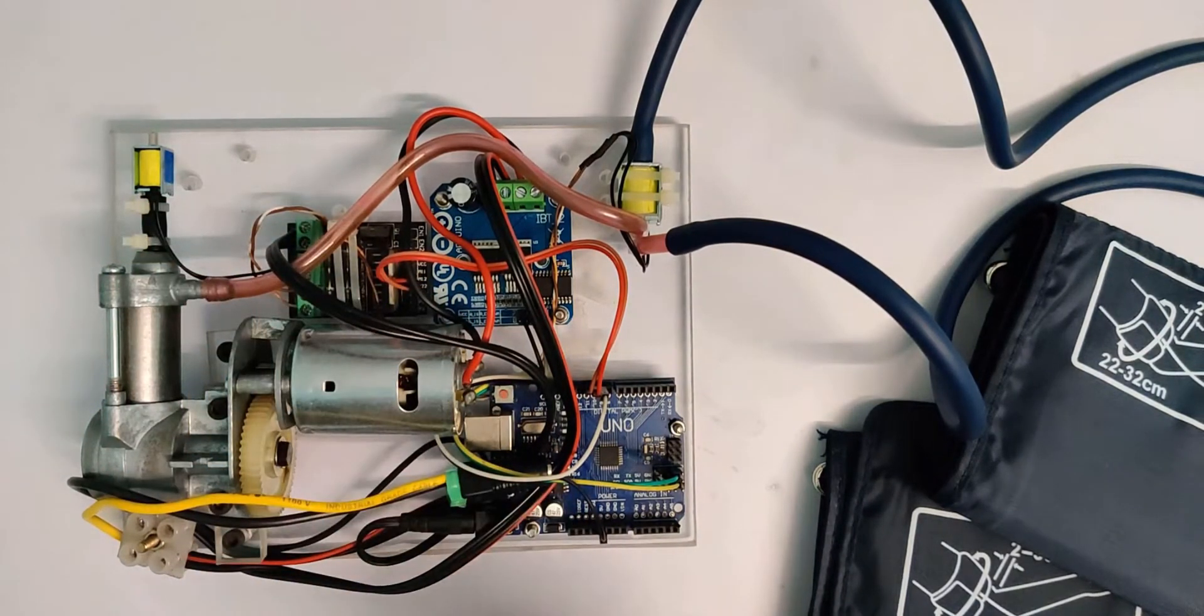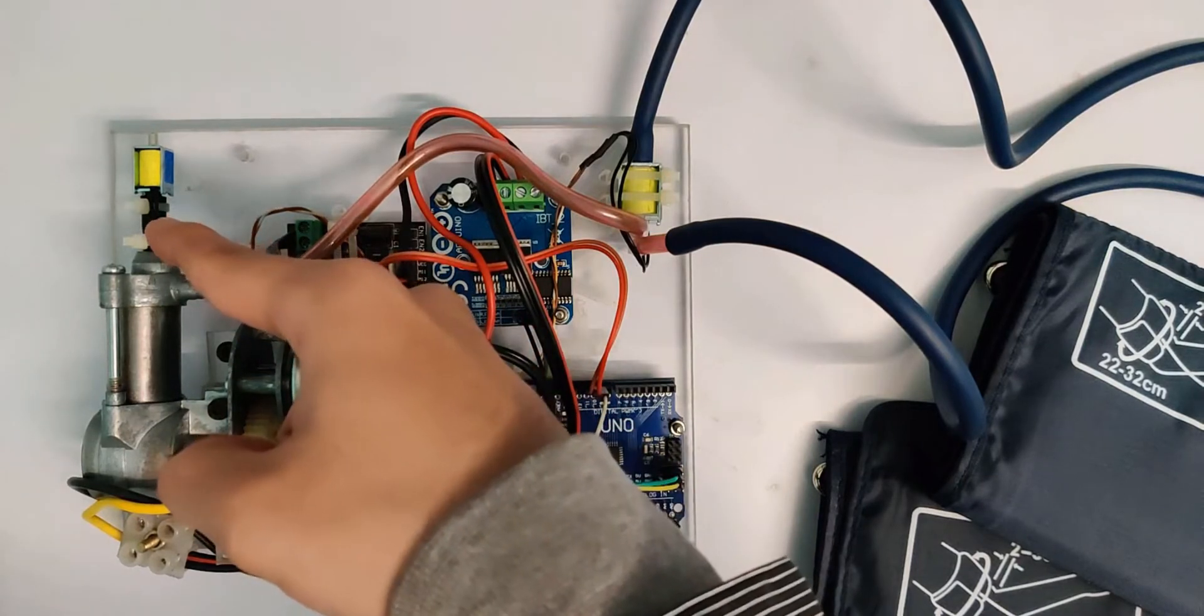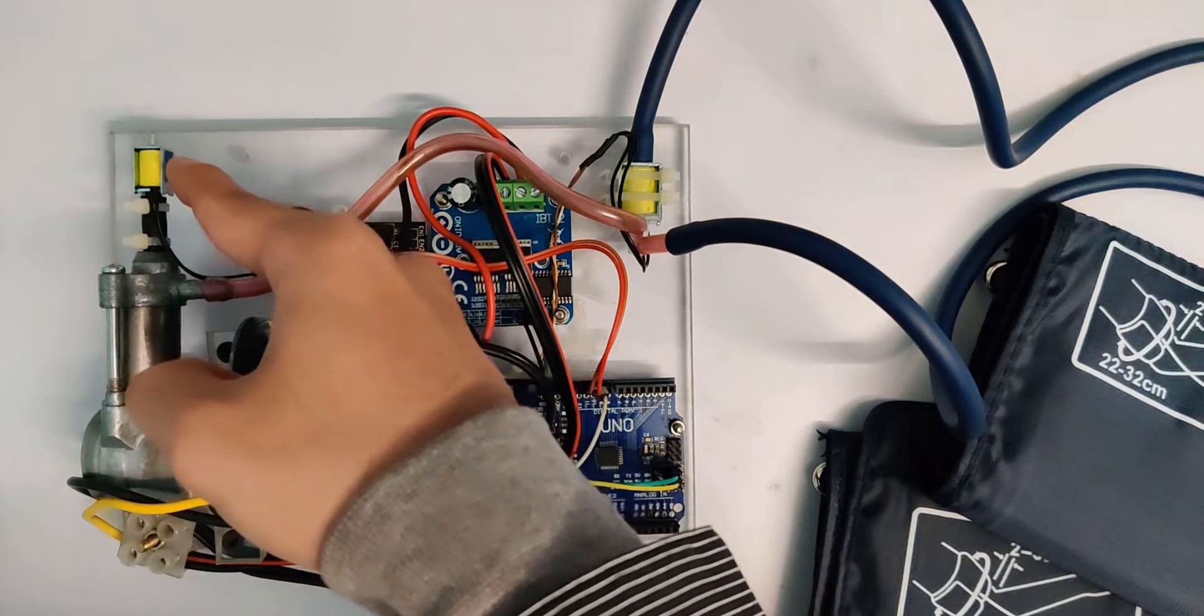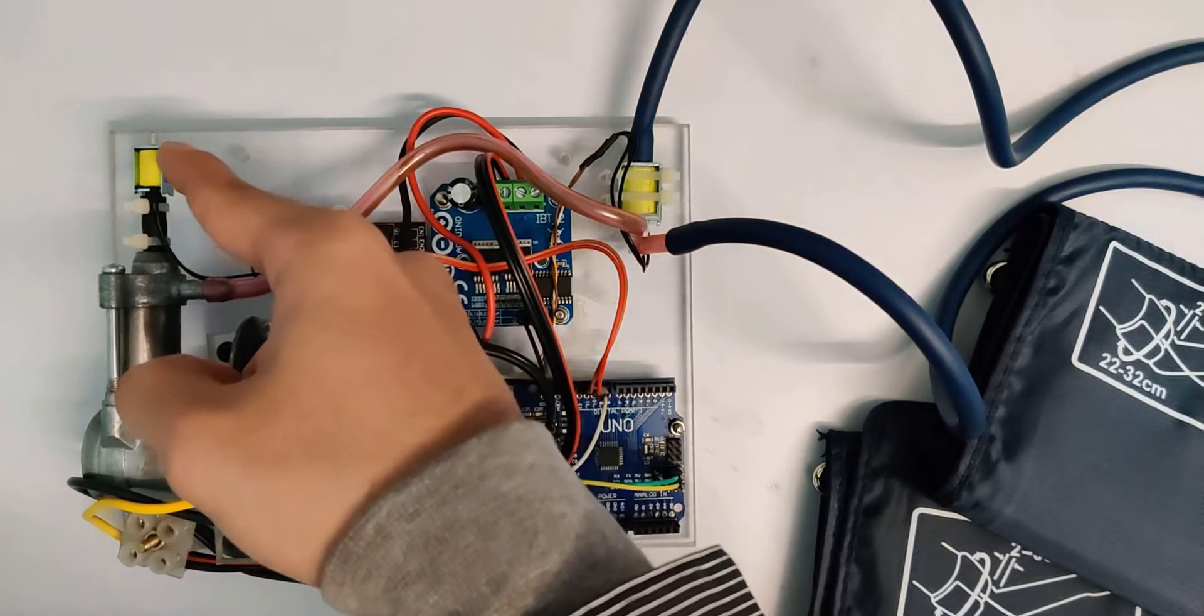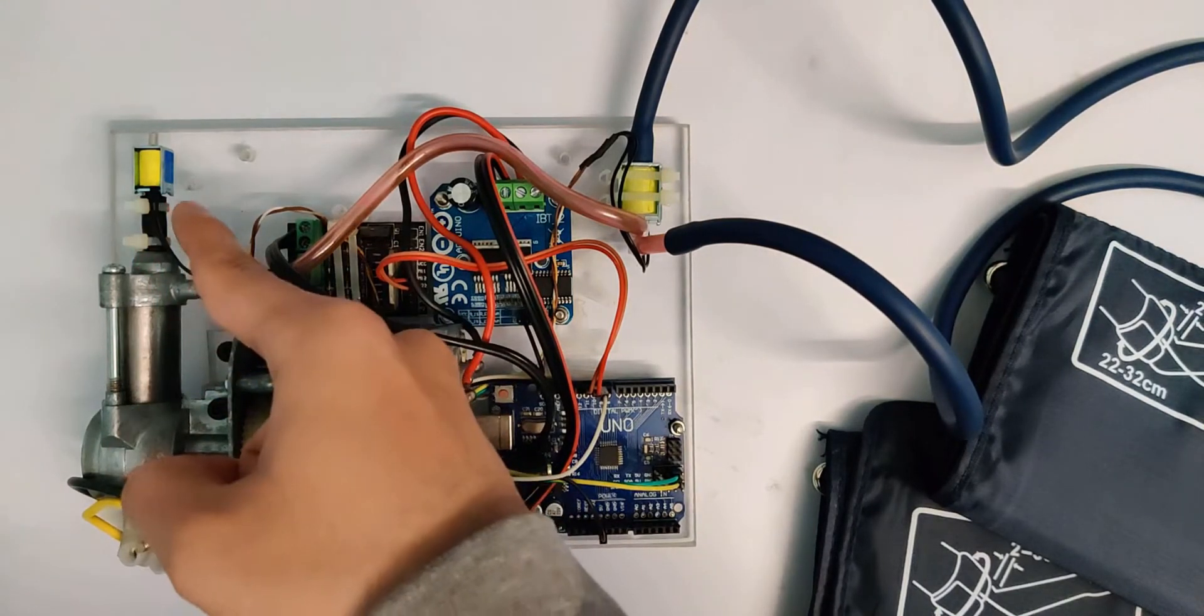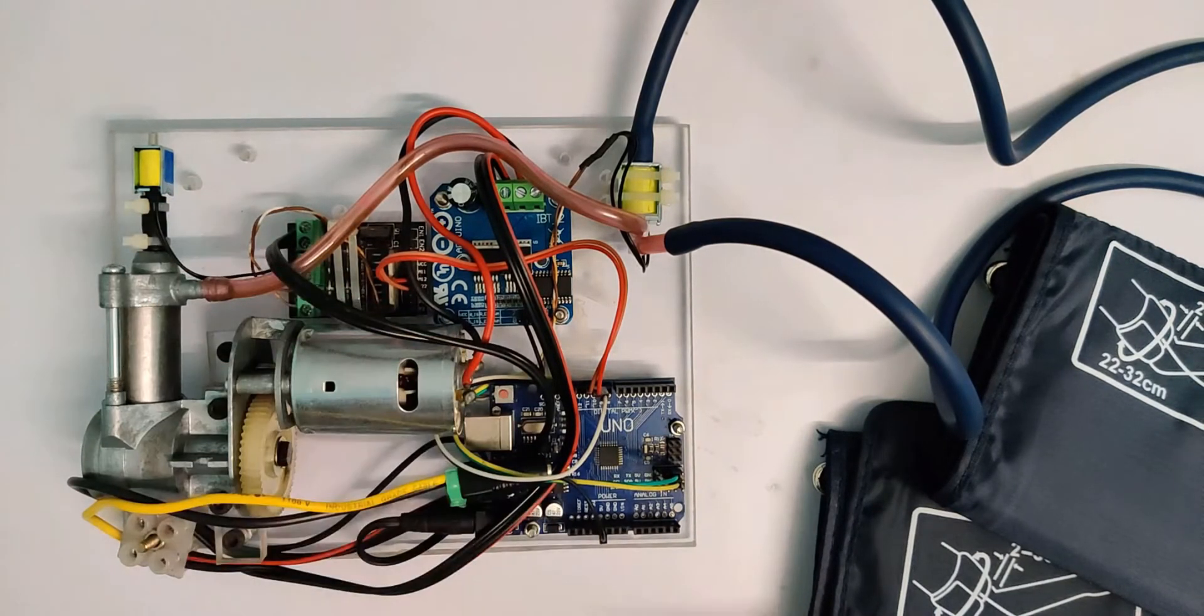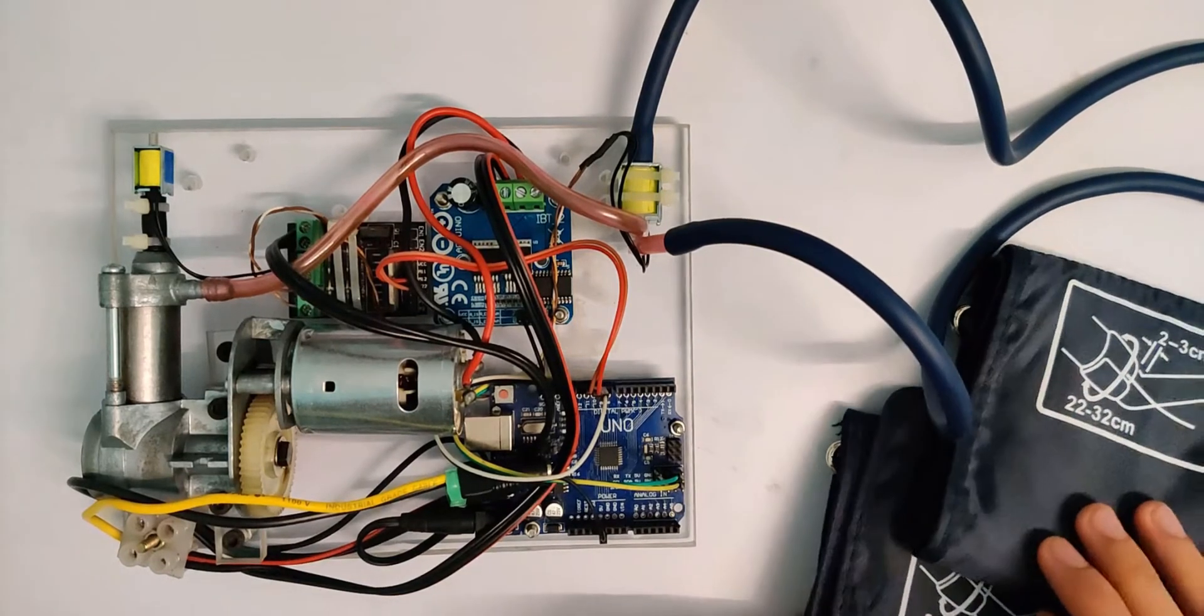An air pressure gauge was attached to this outlet but I replaced it with this small little thing which is a two-way two-position solenoid valve. This solenoid valve opens whenever you want to deflate these two cuffs.